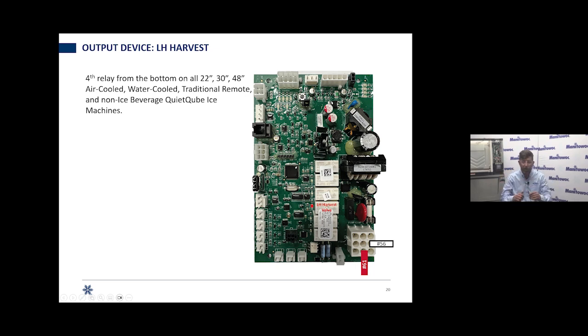That left-hand harvest valve relay is energizing both of those valves. It will also energize an HPR solenoid valve on a traditional remote that utilizes the HPR system. And if you've got power to one, you should have power to both. You could check for power coming from wire 61, it's a red wire, and wire 56.